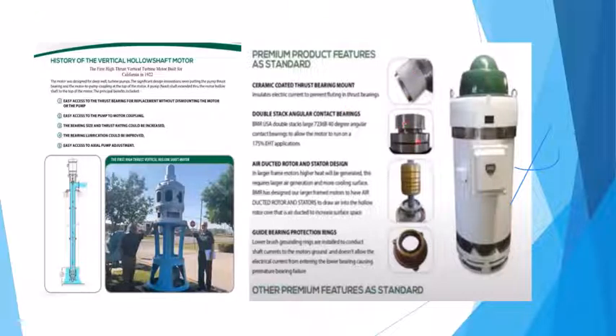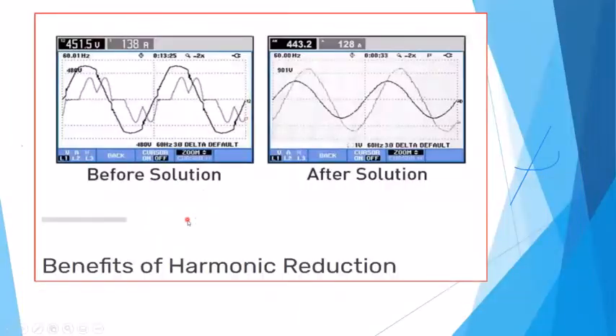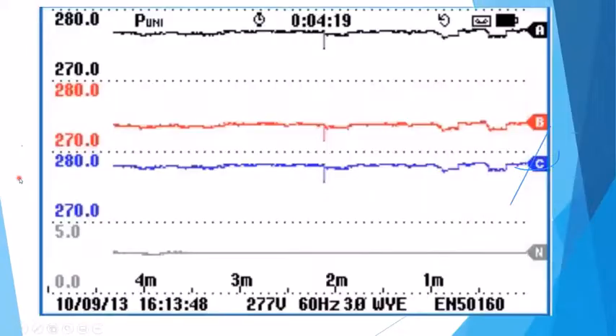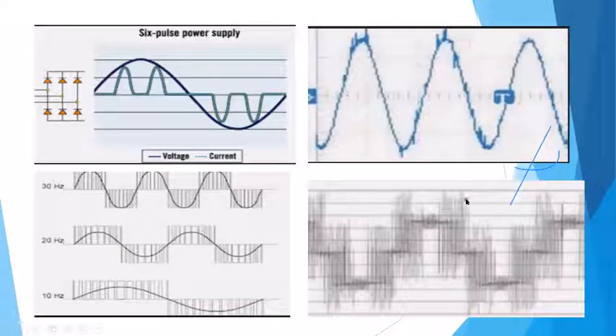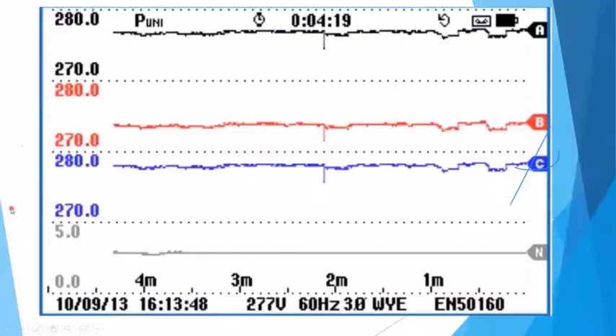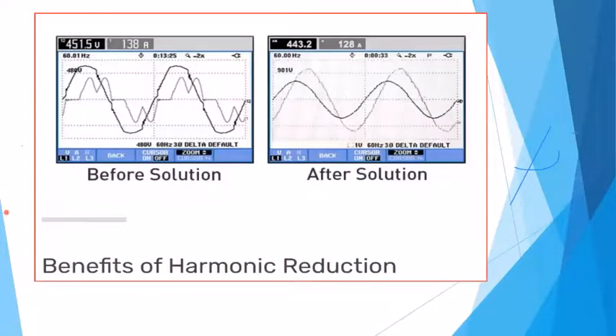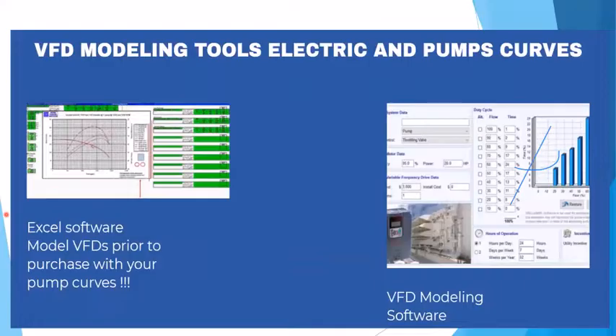But they actually went to where they insulated the mechanical bearings. They also put in brush rings or grounding rings, which you'll hear talked about in different motors, that basically take off that static, this static peaking power coming off of a VFD. That's why they're worried about that peaking voltage, because the insulation may have been designed for 1200 volts, and all of a sudden it's instantaneously sending it 1500, 1600 over a period of time. It deteriorates the actual insulation in the motor and the wires going down the well. And the longer that lead length is, the higher the values will be.